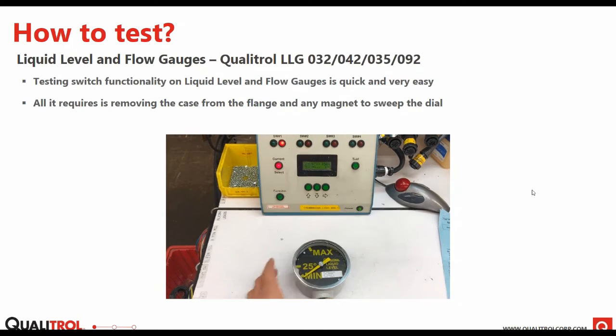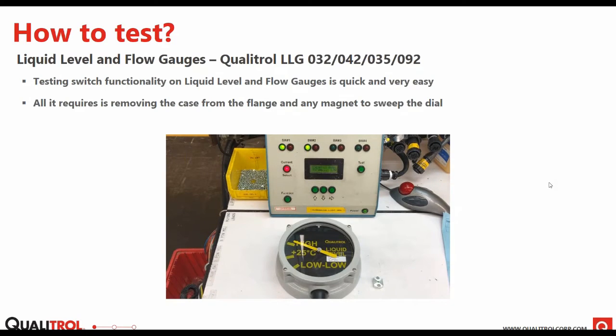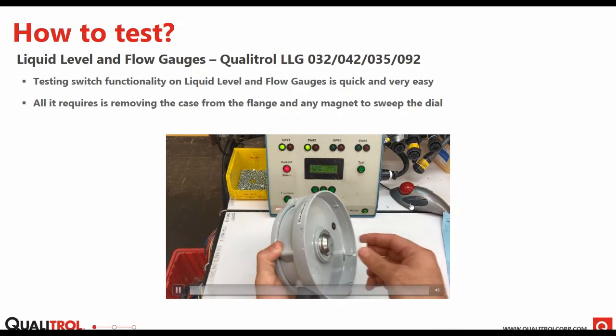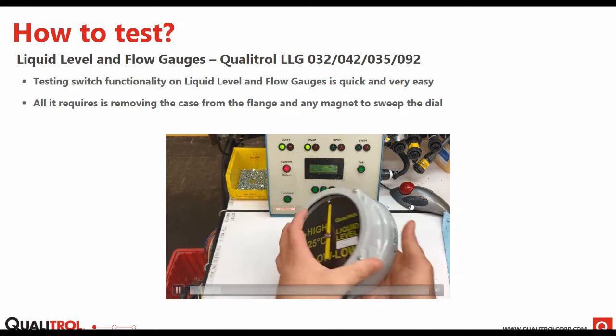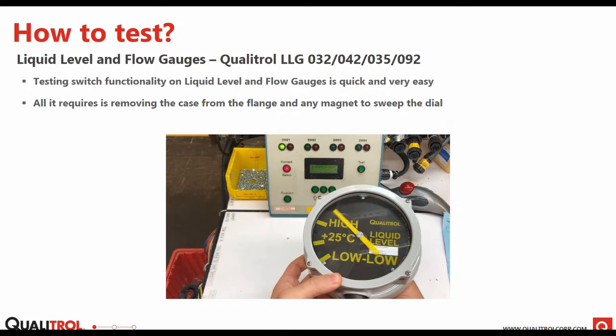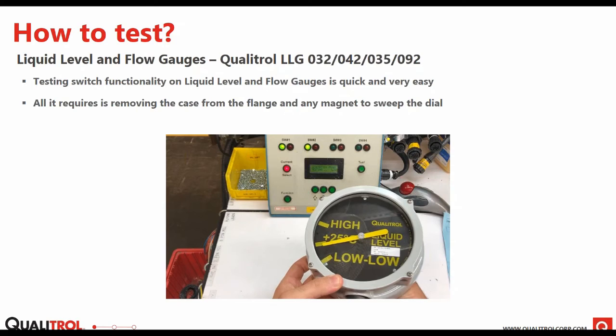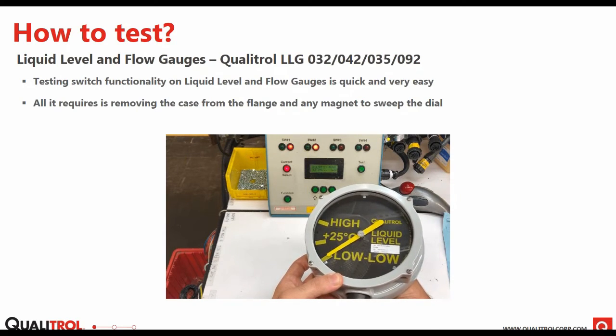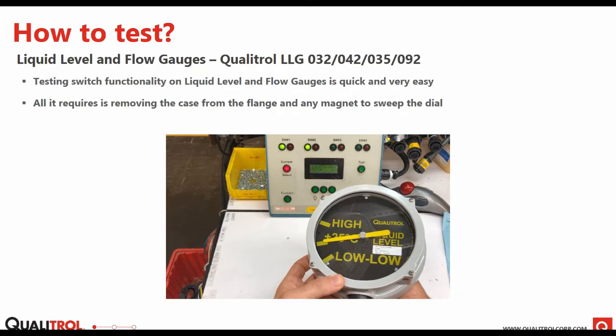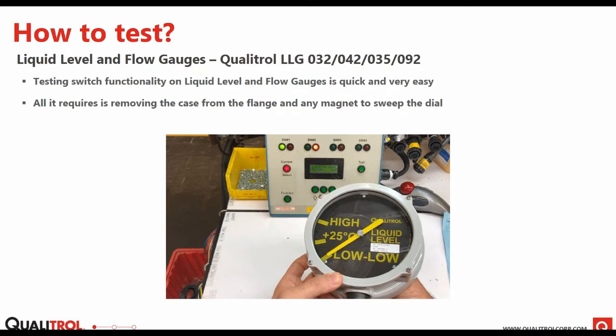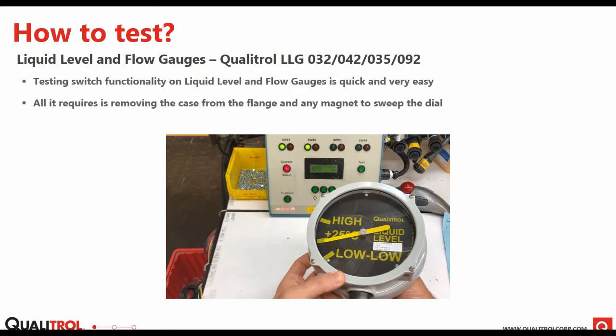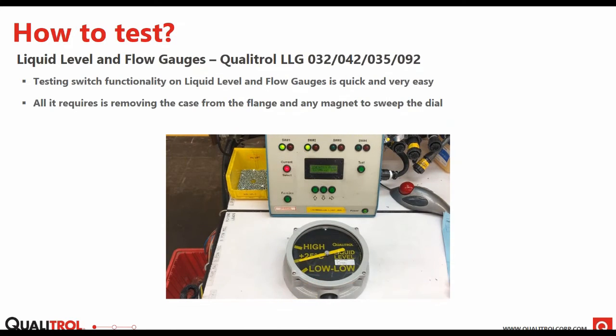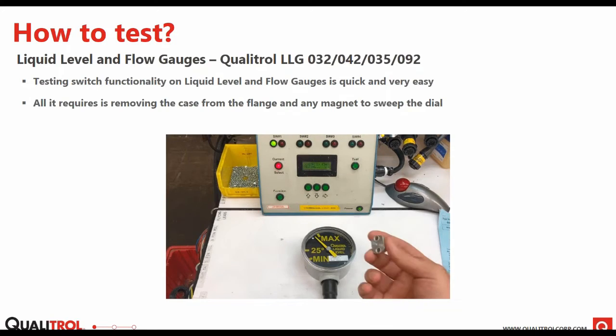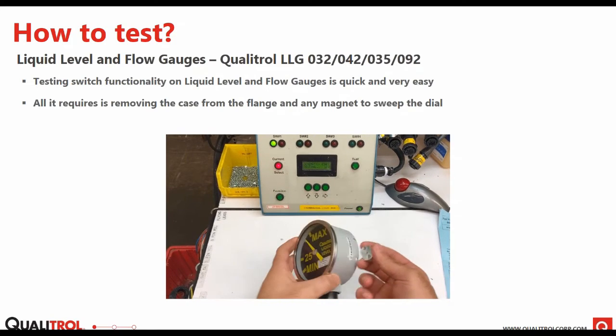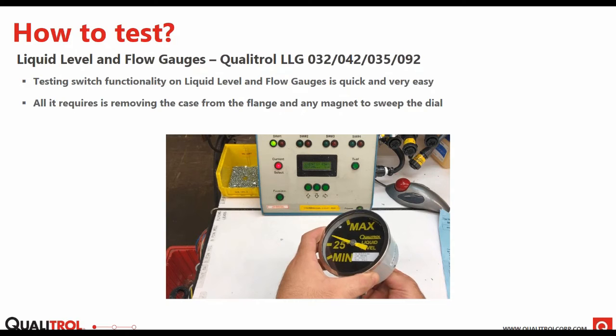So one thing to note with the liquid level gauges is that the part of the gauge that takes the most environmental wear and is out and exposed is the case. So the flange is covered up by the case on the outside of the tank, and then the rest of the flange is internal, which is most of the time submerged in oil. So doing a full functionality test on the flange itself most of the time isn't accessible or necessary. And for how simple it is to test the liquid level gauge, most of the time this is a great way to see if those contacts are still working and they're functioning at the levels where you think they are and where you want them to be.